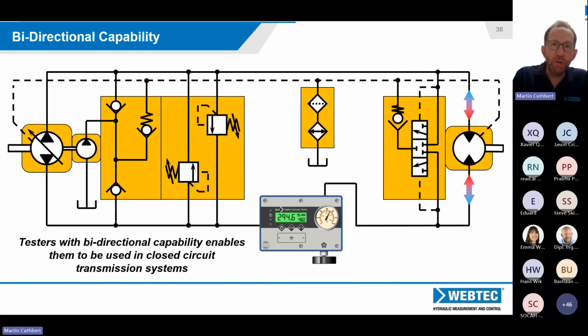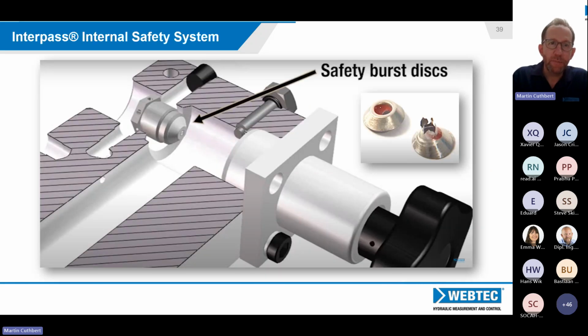If we just elaborate on the Interpass safety burst disc system, you can see in that little picture an example of two of the burst discs and how they petal out when they burst. There's no parts lost inside the system, it all stays together. They're a calibrated disc, so don't ever substitute them for non-genuine parts or another solid disc of metal, otherwise it will render the safety system useless. They just sit on the olive indicated there and allow the oil to pass internally.